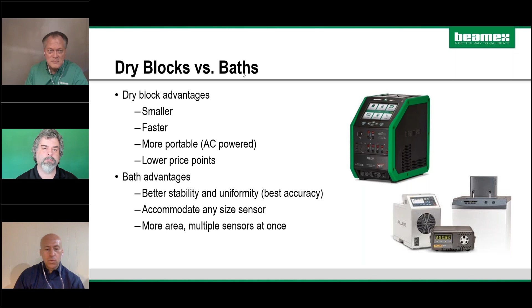I would say it's once a year. Roy, what do you say? I would agree. There's going to be a certain uncertainty if you have it calibrated once a year, but if you wait 2 years, that uncertainty will grow. Once a year is normal. Beamex explicitly specifies a 1-year uncertainty, so our published specifications are valid for once a year.